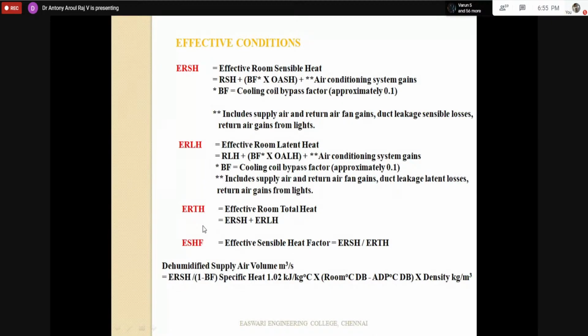Then what is required for me is to find the effective room sensible heat factor, because if I know the slope, only then can we hit the saturation line and find the ADP, and you can substitute that ADP to find the dehumidified CFM.